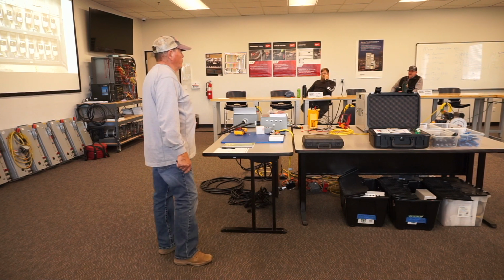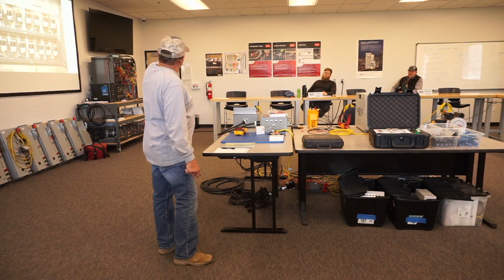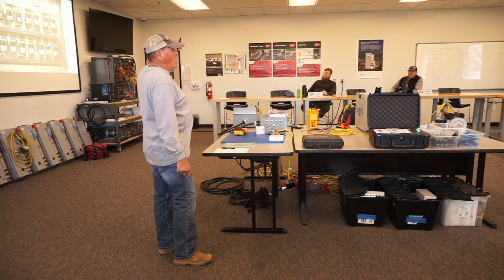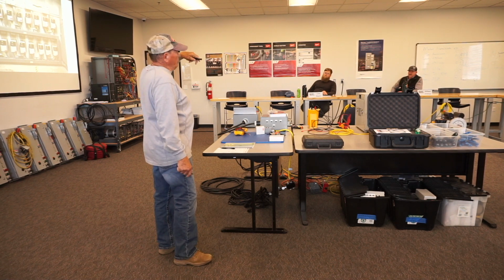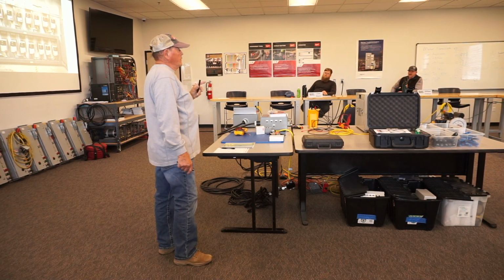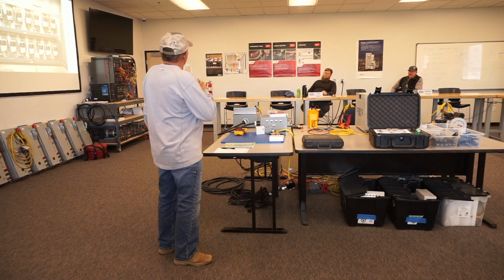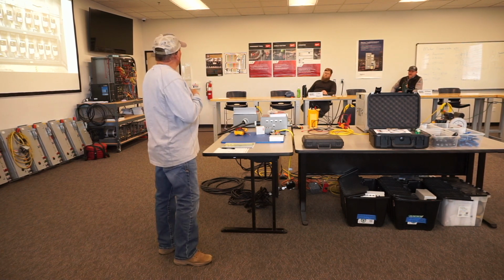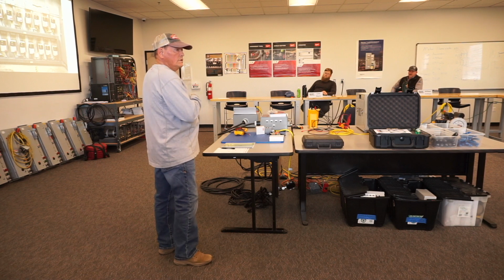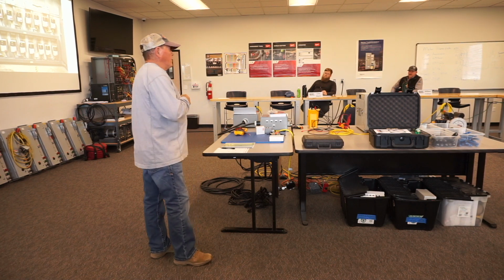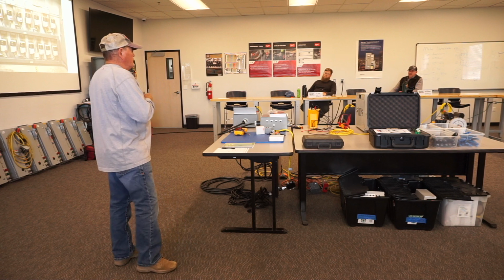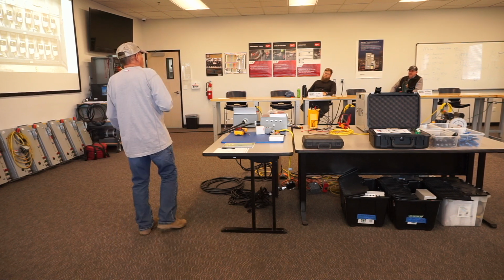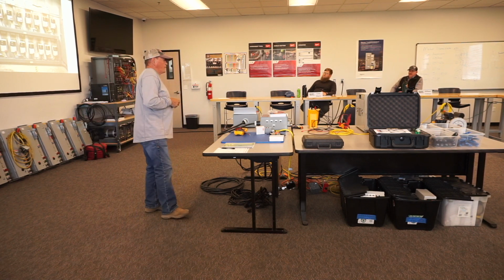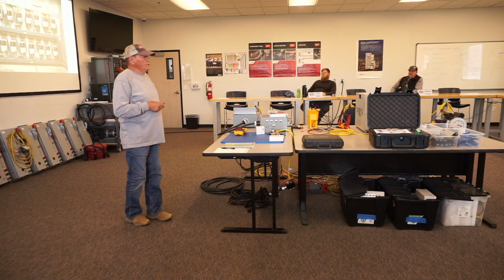You know, you're on a piece of equipment, a variable air volume box that controls the amount of air that flows in this room. Got a microprocessor in there. I gotta get 120 to that motor, and I gotta get a control wire to the motor. I'm just gonna stick it in the same conduit.